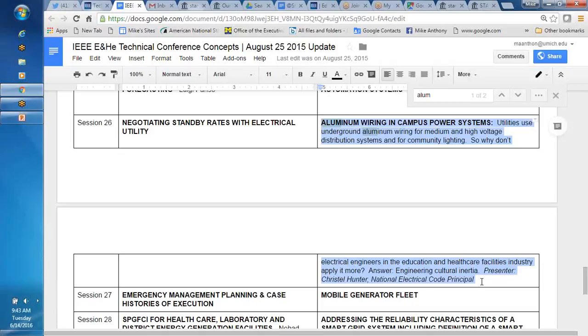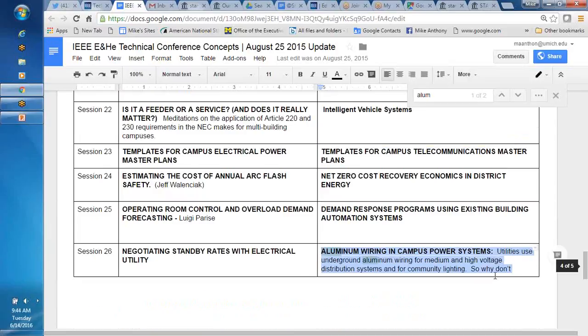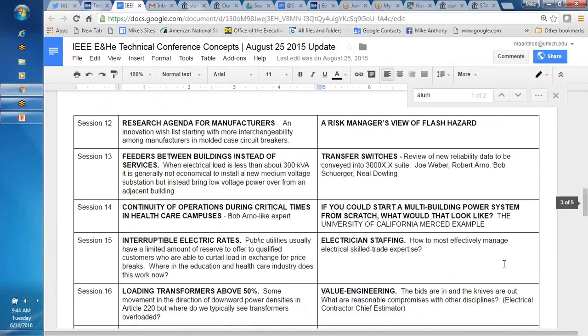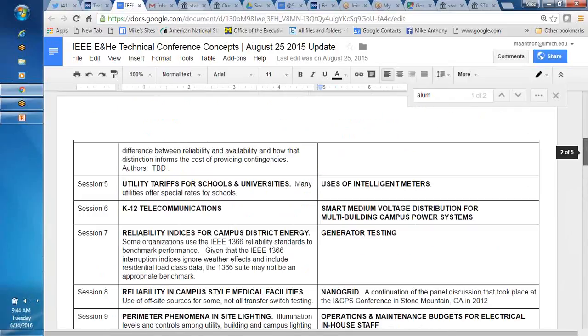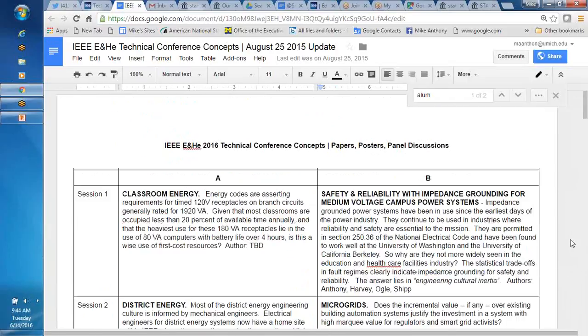So there might be other reasons for using aluminum wiring, just the cost itself. Now, you're limited by your duct, and that's the biggest issue for us. Right. And on top of that, my understanding, and maybe I'm wrong about this, is that you need a larger profile cable to carry the same load as the equivalent copper. We get that. We know that. We saw that coming, and that's why we bore down on the transformer sizing.